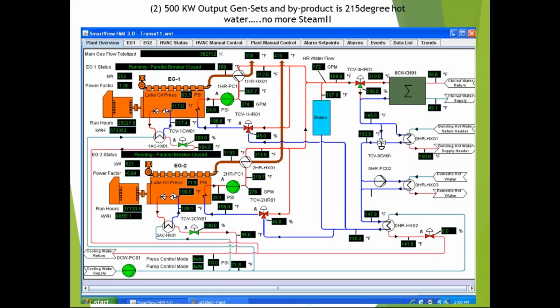It sends the piping system, jacket water system, goes through a plate and frame heat exchanger. That's my building heating hot water. That's comfort heat. So what that does is that supplies heating reheat coils on my perimeters. That's pretty common in San Francisco and other parts, I'm sure. Then whatever is left over goes through domestic hot water. That's just a little shell and tube. Office buildings, they don't have a lot of hot water demands, right? It's just bathroom sinks, and that's it. If a tenant has like major dishwashers, you put in like little spot heaters and such and such.